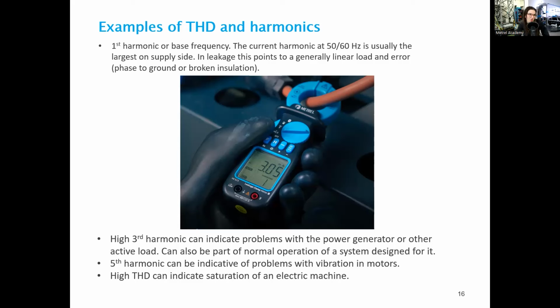Filtering to the first harmonic will show the linear effects in the installation. So this will exclude all effects of higher frequency content, and it removes any distortion. So leakage in the first harmonic will show us linear faults like phase to ground contact, broken insulation, trouble with heaters, and similar issues. Now, if we find an unexpected third harmonic, it can indicate problems with power generators or other active loads. In the case of power generators, it has to be stressed that the third harmonic usually does not mean magnetic problems, but some other type. I already also mentioned that a high third harmonic can be part of the normal operation of a system in case it is designed for it.